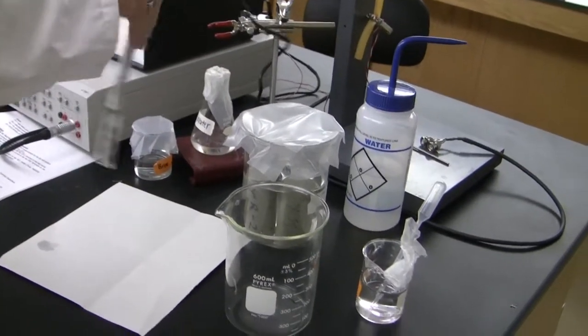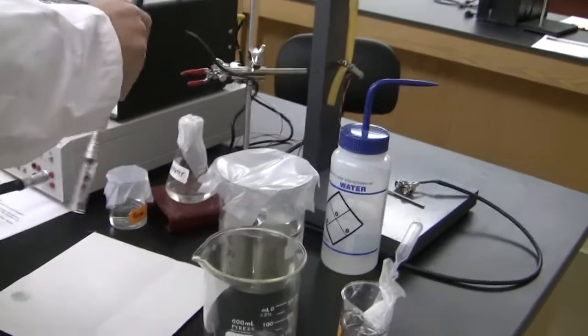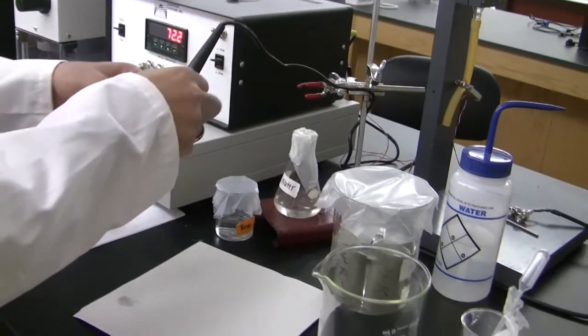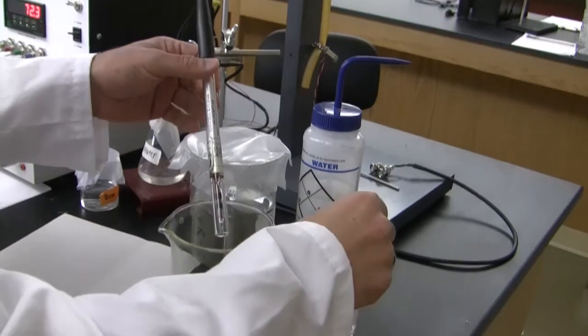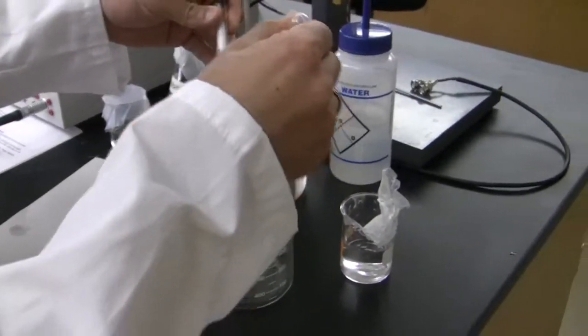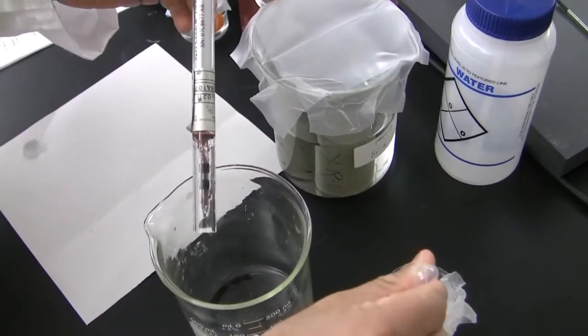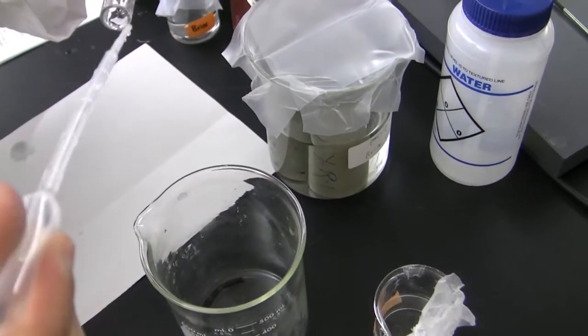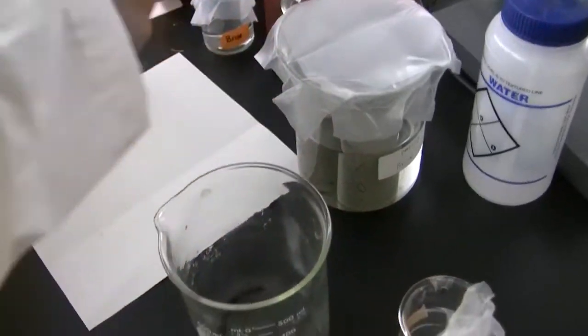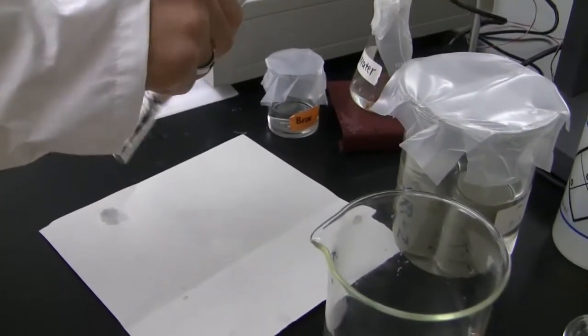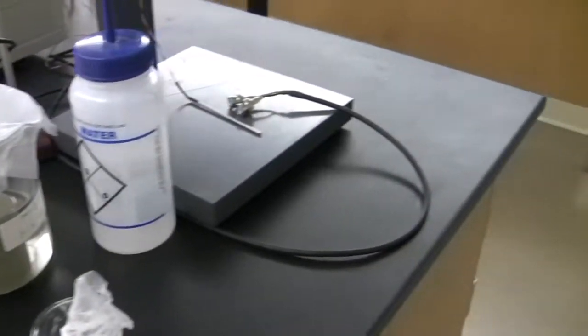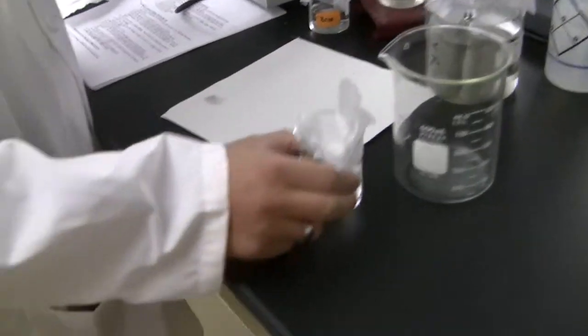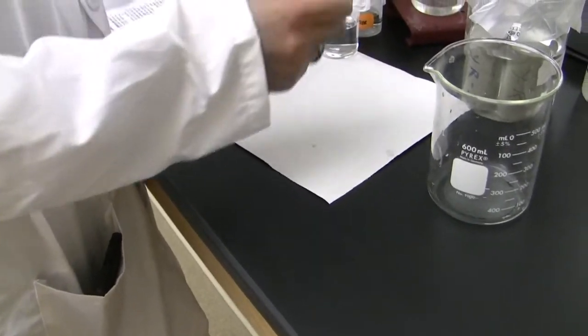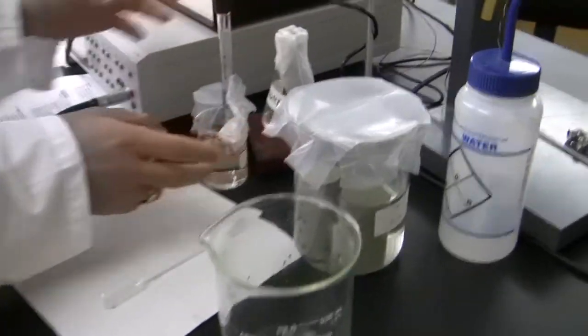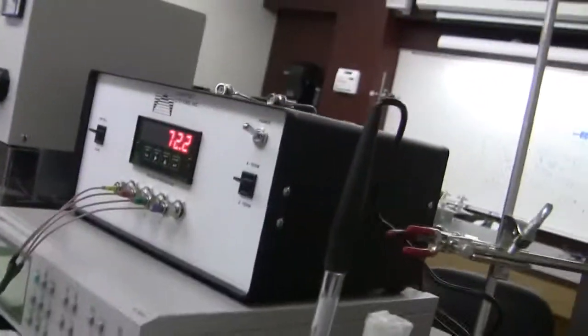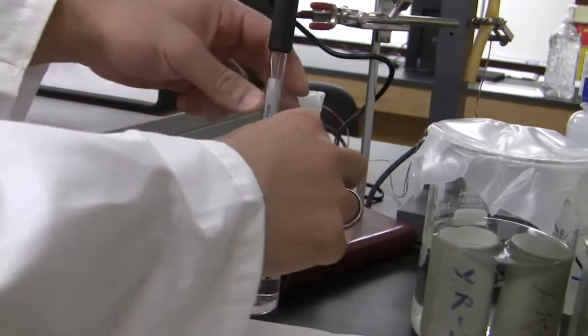So you take it out, just shake it. And then maybe for accuracy, we can also rinse it with brine. And then you can put it in your beaker of brine. You can use it. It's better, of course, if you use fresh brine that you didn't touch, but this one should be fine. It needs to be at least 2 inches of brine in there. And try to hold it in an upright position without falling to any sides.